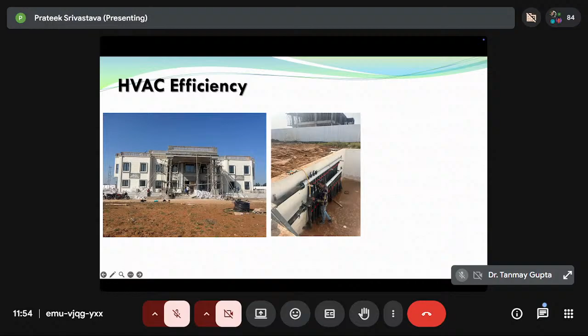All 20 bore pipes come from the ground to this point, and from this point, if you see these black pipes, they go to the plant. Here we have a geothermal reversible water to water heat pump. If you see this photograph, this is a heating application. Usually when we do heating through a VRF system, we get a COP of around 3 or 3.5. If we do heating from a boiler, we usually get a COP of less than 1. From this system, we are getting a COP of around 8. For getting 72 kilowatt of heating output, we are consuming just 9.9 kilowatt of energy.